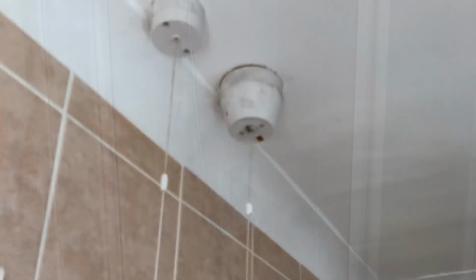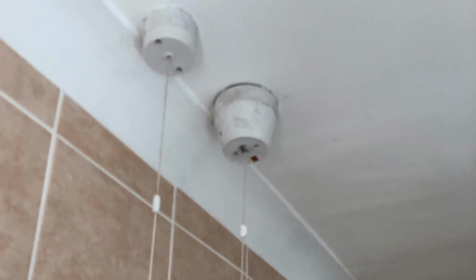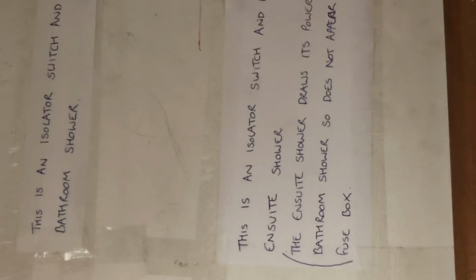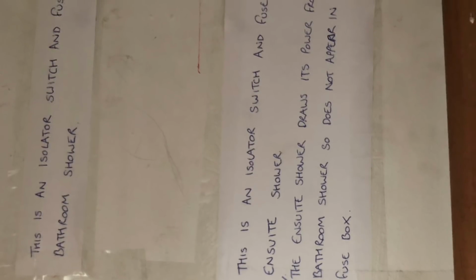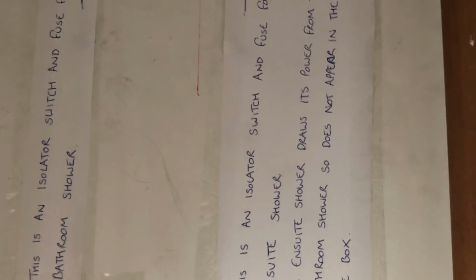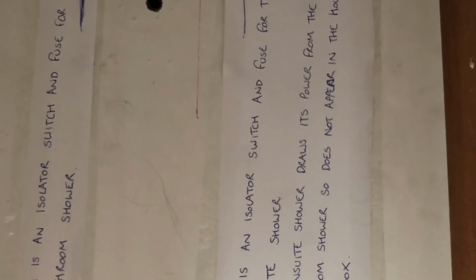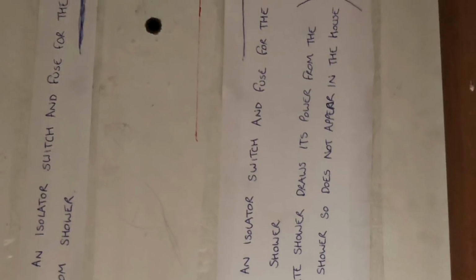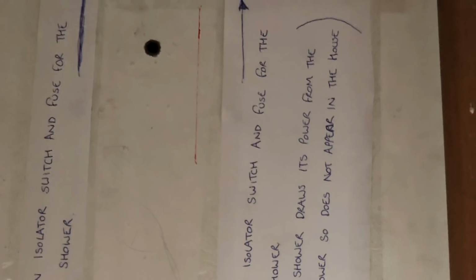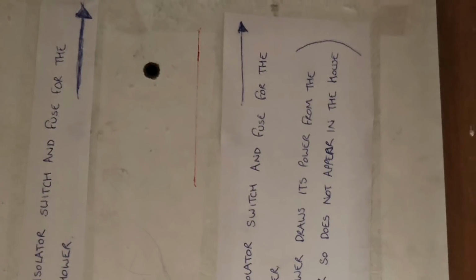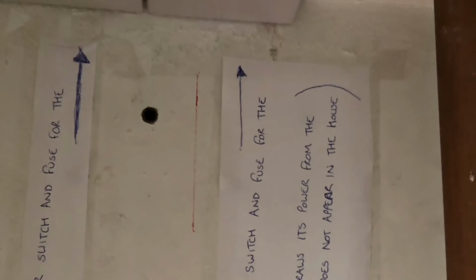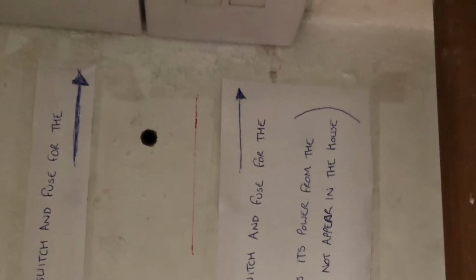And here's the shower that British Gas fitted, along with the isolator switch, which is a 50 amp proper power shower switch. Interestingly, in one cupboard I found this, which said it was the isolator switch and fuse for the ensuite shower. And it was turned on, but the fuse had blown. So that was why there was no power going to it. But it was still not safe because there was no RCD protection and the wiring looked really dodgy. So I recommended an EICR, and we'll see what they want to do after that.